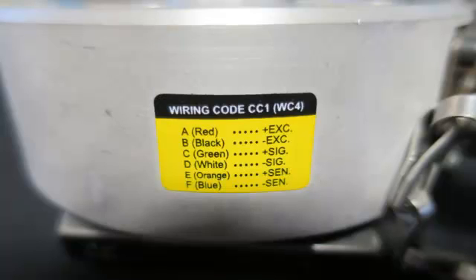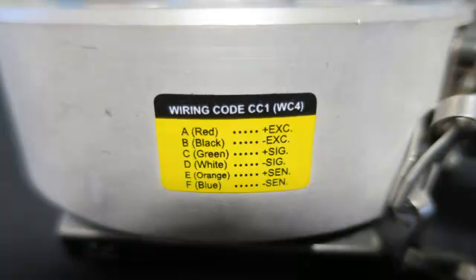This load cell has 6 wires. Red and black are plus and minus DC power. Green and white are plus and minus signal output. And orange and blue are the sense lines. What the sense lines do is supply a feedback voltage to compensate for IR drops over long wire runs. For short wire runs, they are not needed and will not be used today.